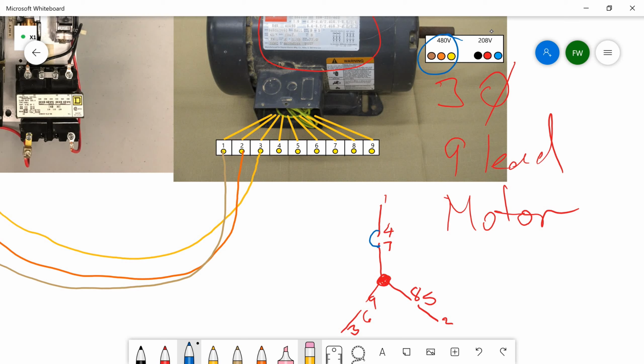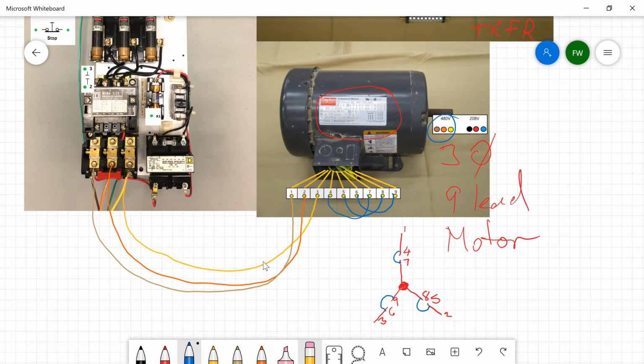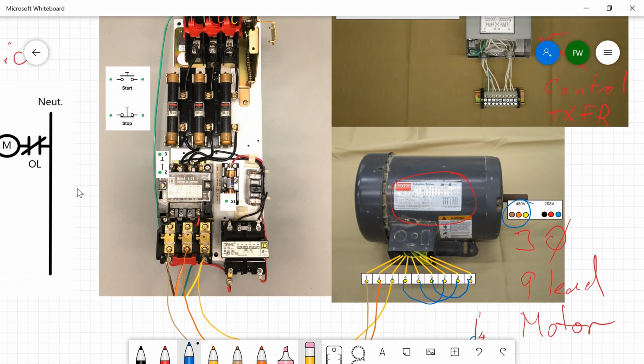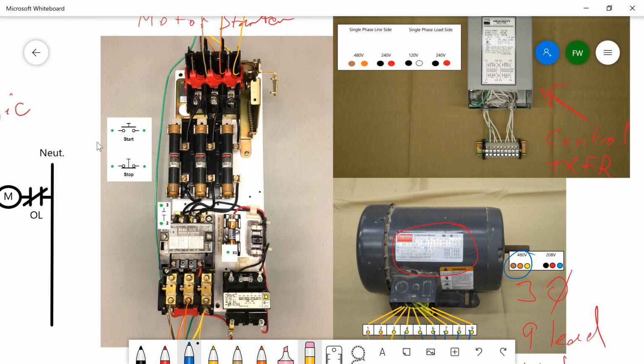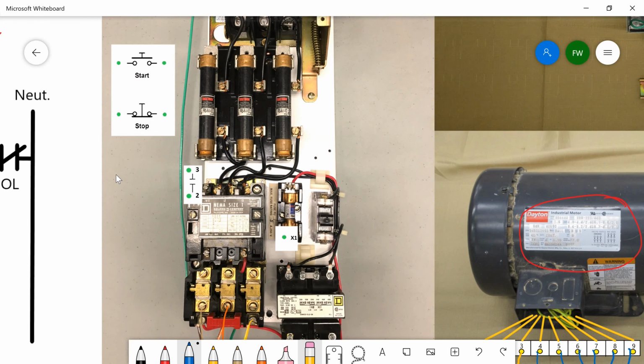We're going to hook 4 to 7, 8 to 5, and 9 to 6. So over here we have 4 to 7. We're going to essentially splice those together. We're going to go 5 to 8 and 6 to 9. And that will complete the motor hookup and your 3-phase 3-wire system coming in and out. Now the more complicated part is hooking up the start-stop that actually controls the contactor. So the contactor is this guy right here. He does all the work.